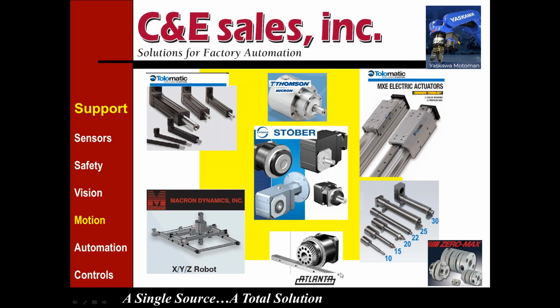Down to the right, we've got couplings. We've got, in the middle, gear reducers from Stober, both in a planetary or power transmission design that we can help select, even if your application is servo-based, but it's a large high inertia load. We can combine a power transmission gear reducer with a servo if you're doing positioning with that high inertia. Let's say it's a chain conveyor, for example, a heavy gauge chain conveyor. This is a perfect solution for that. At the top, I show a stainless steel gear reducer, planetary, if you will, that goes along with that Kollmorgen stainless servo that I mentioned.